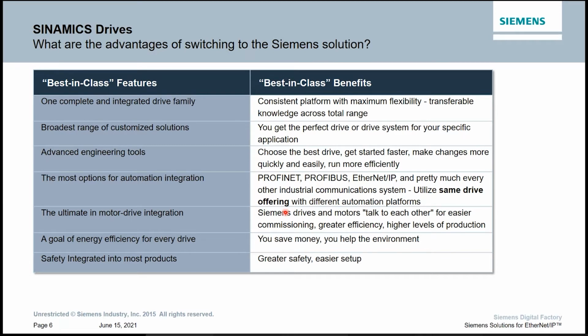The most options for automation integration. We already talked about Profinet, Profibus, and Ethernet IP, so pretty much every other industrial communication system. The ultimate in motor and drive integration: Siemens drives and motors talk to each other. So when you set up a system, you connect to it and say, tell me what's out there, and it configures itself. It also has an advanced motor tuning feature that will tune induction motors and third-party motors very tightly to the drive. They all have a common goal of energy efficiency for each drive, and safety integrated into most products. Not only safety integrated, but network safety, and very easy to set up.